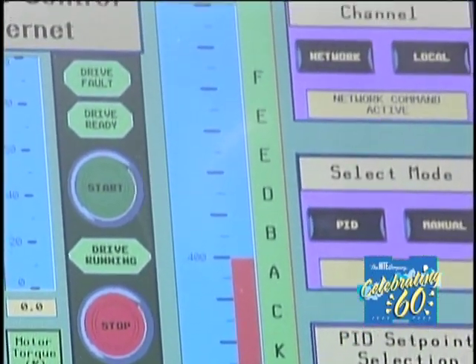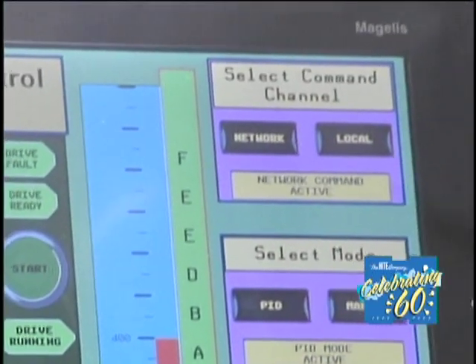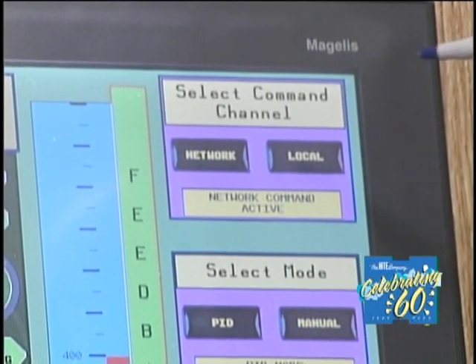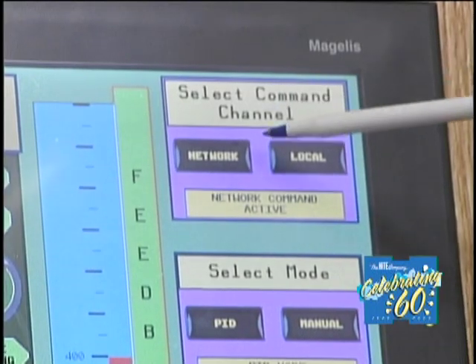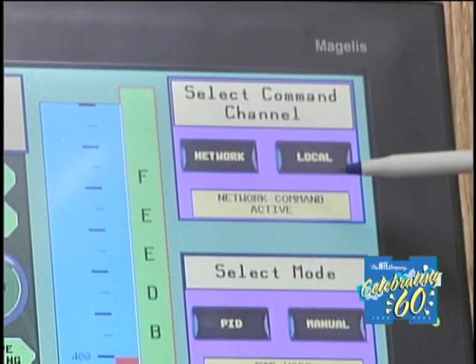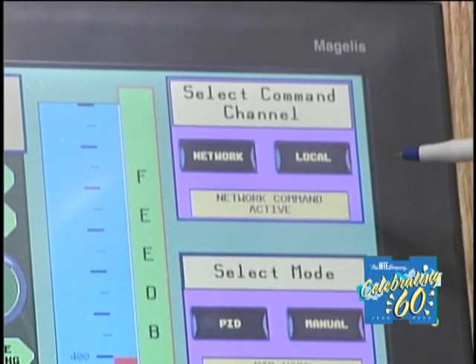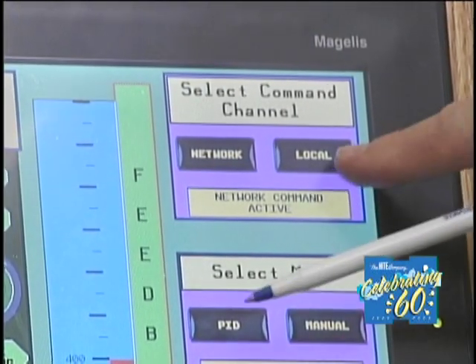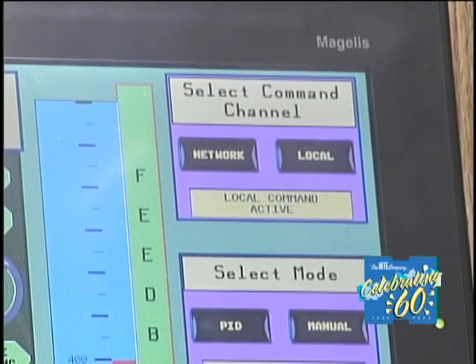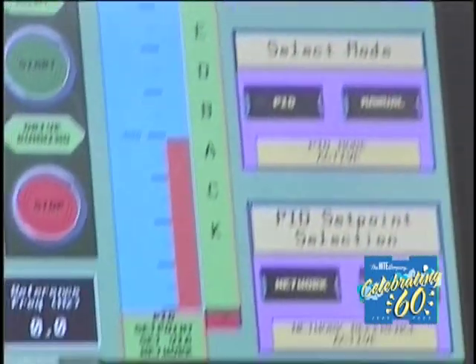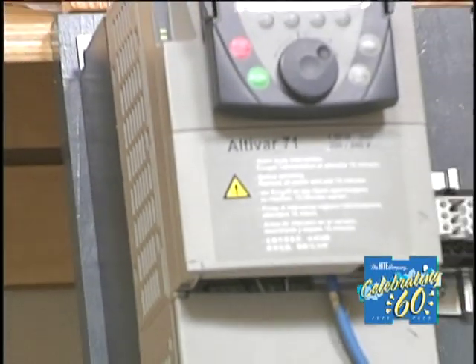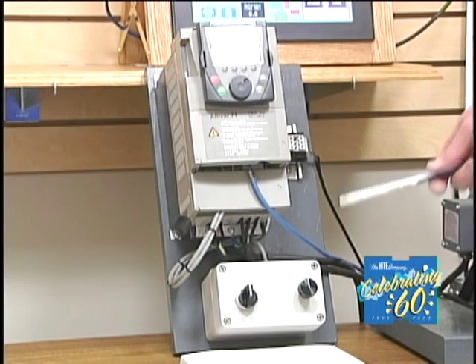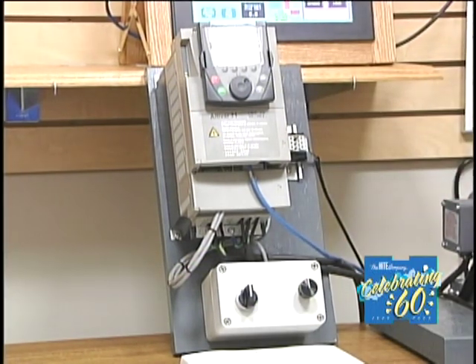On the right-hand side we have some push buttons. At the top is 'Select Command Channel,' which tells the drive where to get its commands. The enunciator showing 'network command' means we're currently using the PLC and touchscreen. If we push 'local,' we jump to the drive itself — specifically the box at the bottom of the drive, which is our local control. In local command, the drive is turned on and off with that selector switch.